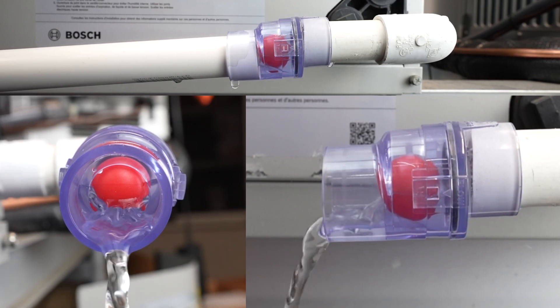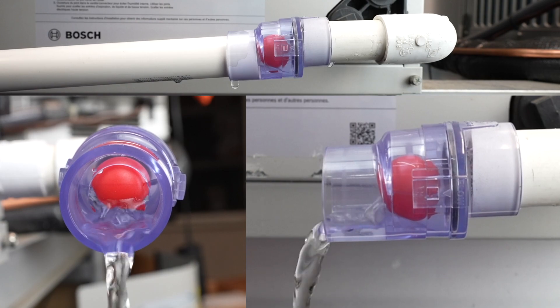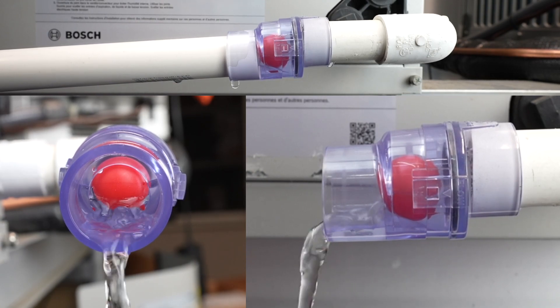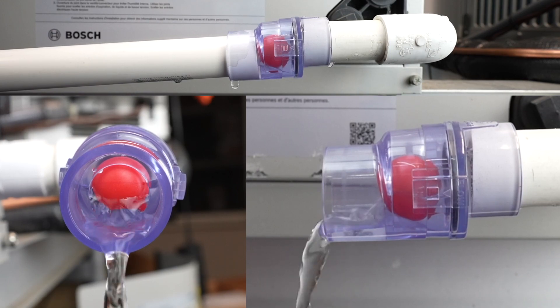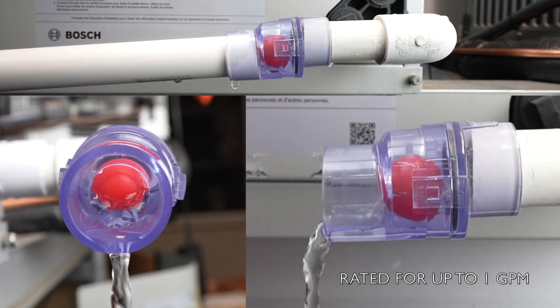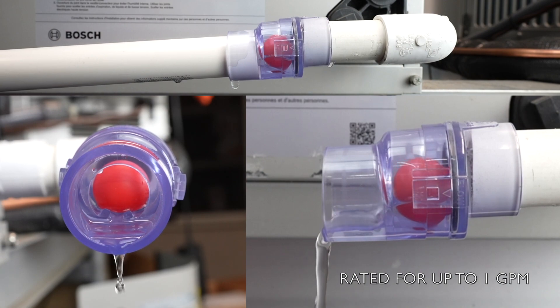Once condensate builds up, it will push the ball valve away from the hole, up the standoffs, allowing the condensate to flow freely past. When no condensate is present, the negative pressure pulls the ball valve against the hole, seals the condensate line, saving energy and eliminating dirty air from entering the system.